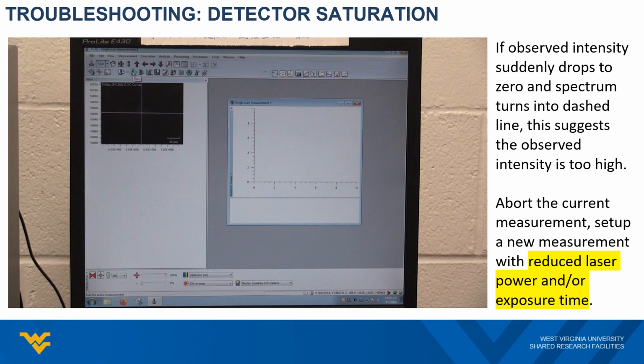One possible issue you might have during the measurement is that the scattered signal is too strong for the detector to handle with the chosen parameters. If that happened, you will see the observed intensity suddenly drop to zero and the spectra turns from solid red curve into dashed red curve, as shown here. If this happens, you will need to abort the measurement, then set up a new measurement using reduced laser power and exposure time, and try it again until you get normal Raman spectra.